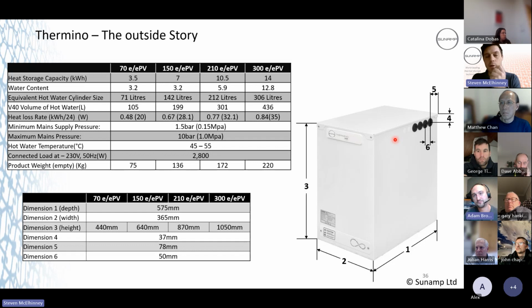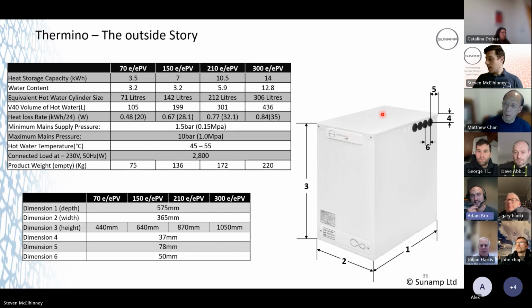The only time you'd be wanting to remove that is to inspect the electrics at the top unit for whatever reason, unless the customer was going to move it or do something else with that space. So as long as you can isolate it and disconnect the pipework safely, you can then roll it forward, and then you can work on the top quite happily. So that's my plan. I'll send some pictures to the company once I've done it, just to make sure everything's sweet. But it's a tough one.